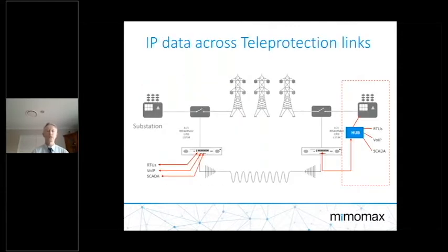So across the teleprotection links, besides the relay switching and sensing and transfer trip type information being sent across the channel in the serial data, we can also provide RTU, VoIP, or SCADA, given we have the capacity to support those applications.